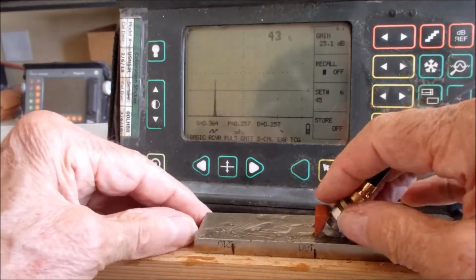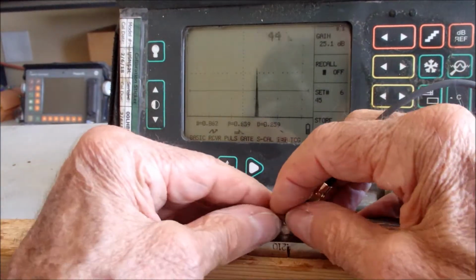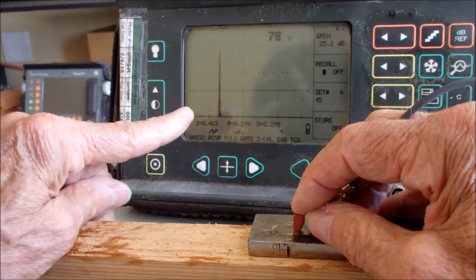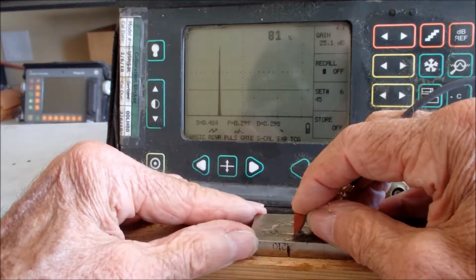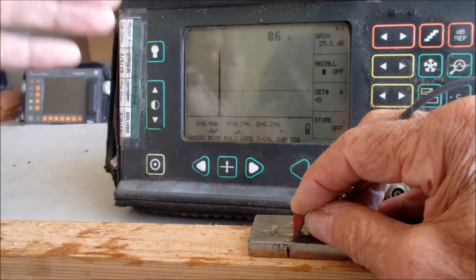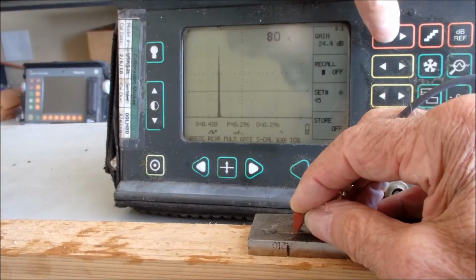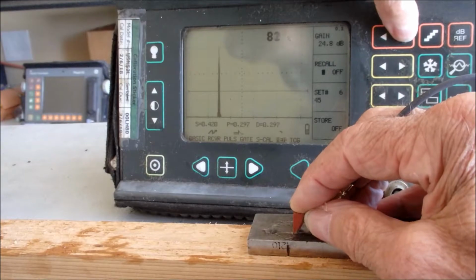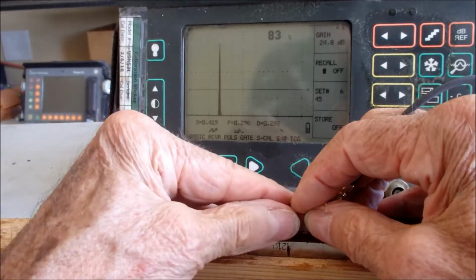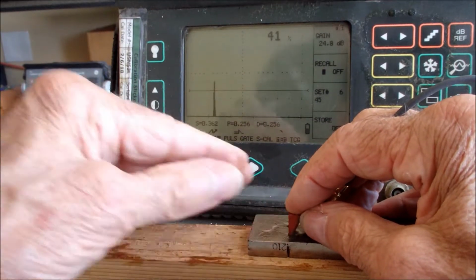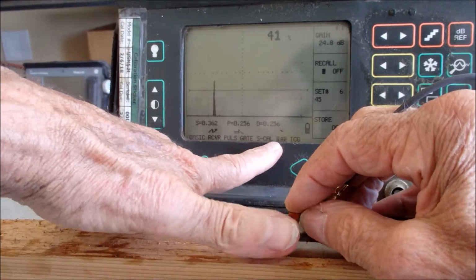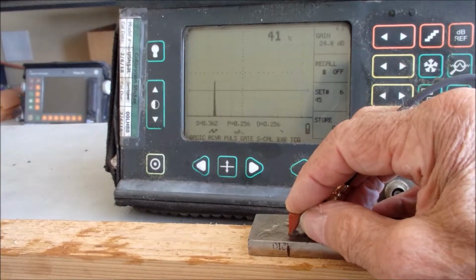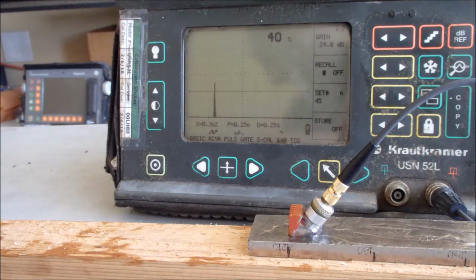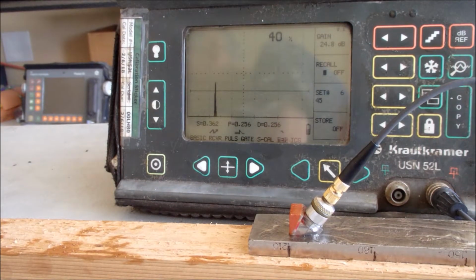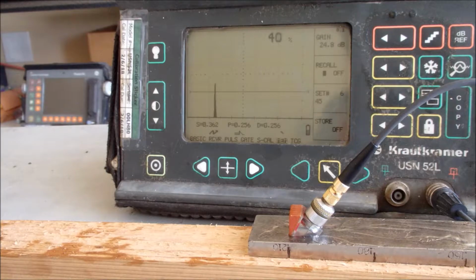180. Let's try the 210 thousandths deep ID notch. There's the corner trap signal from the 210 notch. I'll bring that to 80% screen height. And now I'm going to push forward till that is 40% screen height. That would be a 6 dB drop. That says 256. 300 minus 256 is 44 thousandths. So that's saying it's 44 thousandths when it is 210 thousandths.